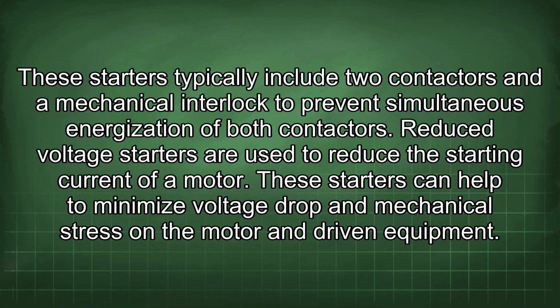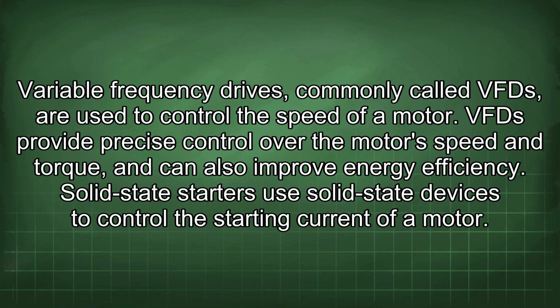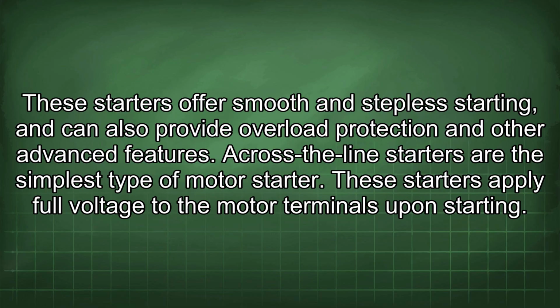Reduced voltage starters are used to reduce the starting current of a motor. These starters can help to minimize voltage drop and mechanical stress on the motor and driven equipment. Variable frequency drives, commonly called VFD, are used to control the speed of a motor. VFD provide precise control over the motor's speed and torque, and can also improve energy efficiency. Solid-state starters use solid-state devices to control the starting current of a motor. These starters offer smooth and stepless starting, and can also provide overload protection and other advanced features.